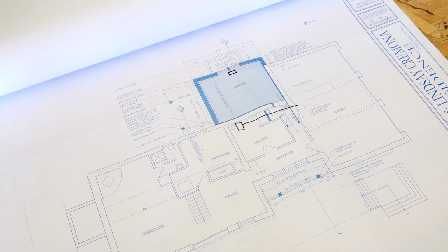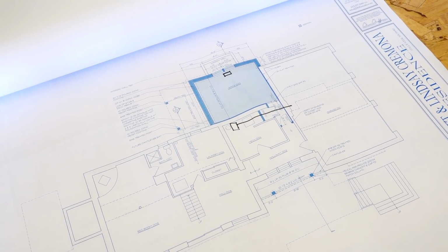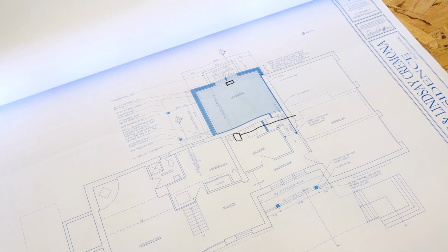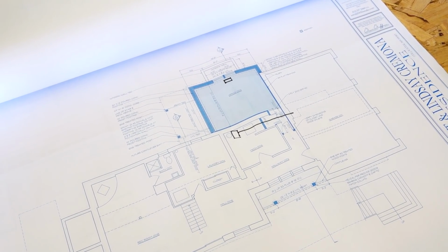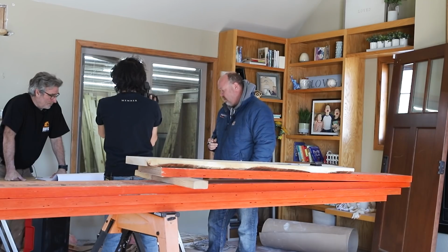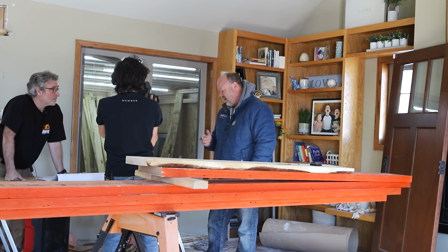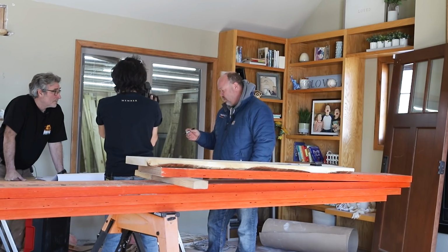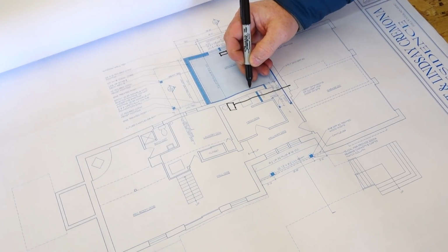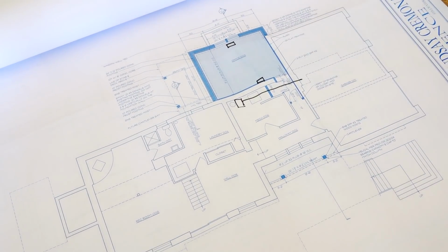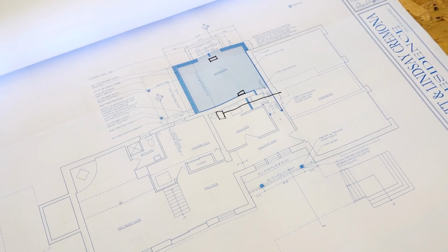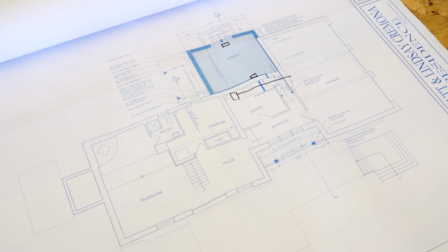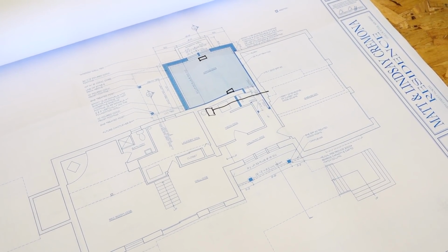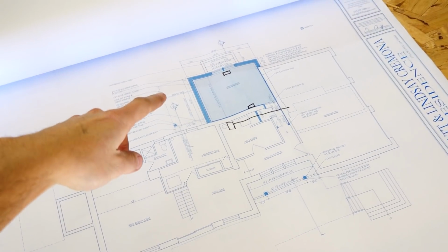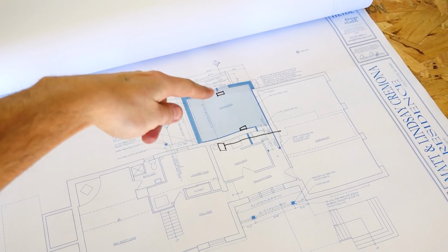So we're going to put a ceiling supply blowing down. The deflection is going to be a double deflection to the right and left, and the throw of the register is designed to have a 15-foot throw. Why that's important is when we have a return coming back through the wall somewhere in this area here, we're going to be able to splash that floor and create a good airflow cross stream across that room that should create comfort. So in theory, the air should be like, I'm coming from here, and I'm going to go to here.